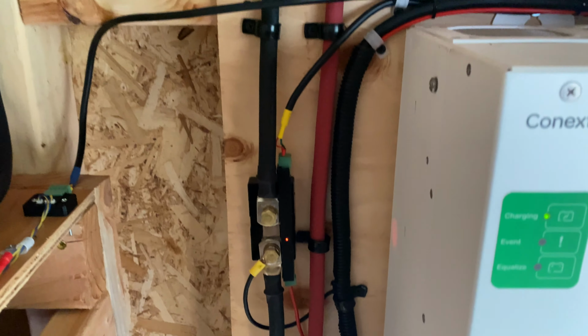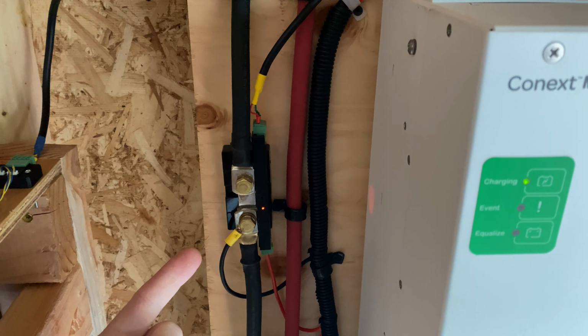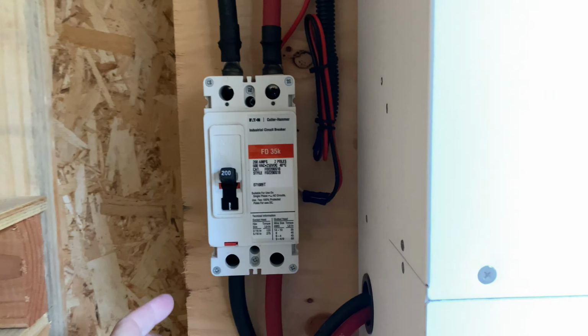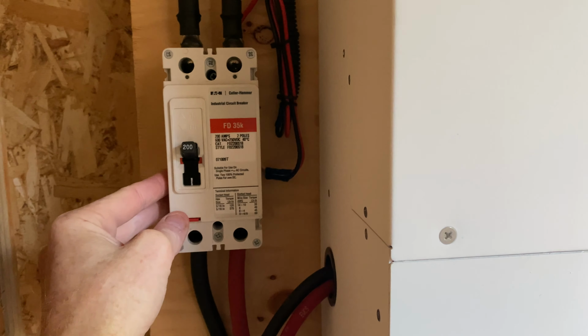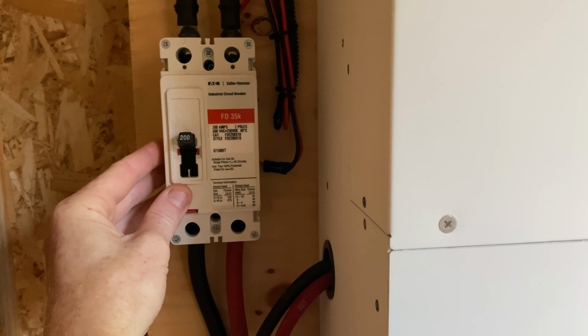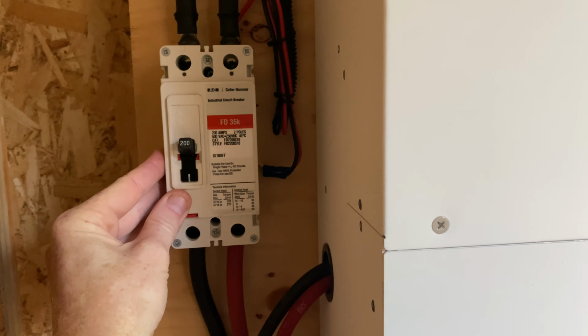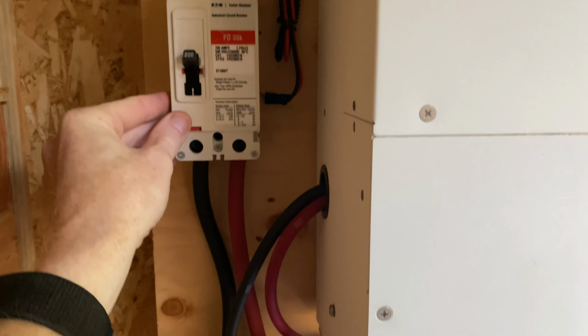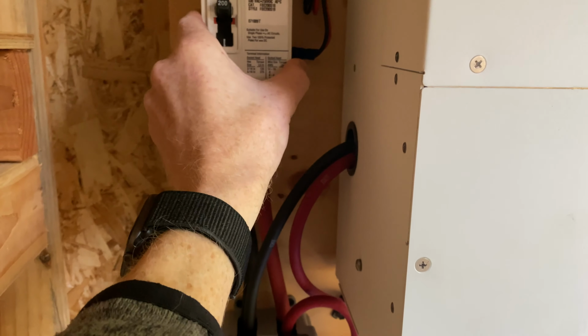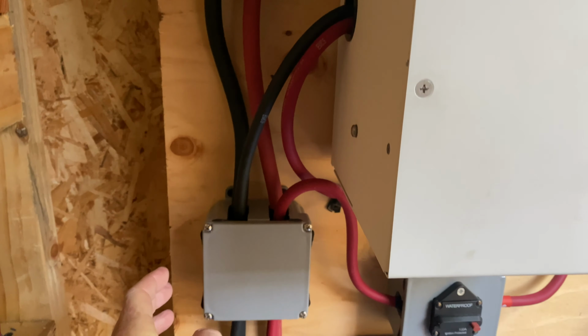If we continue on, obviously we have the shunt for the Batrium. Coming down here, we have the shunt trip breaker, which is controlled by Batrium as well, and this will disconnect all loads and the chargers and all that stuff in case of a critical event. This is 24 volt driven - we'll go into how that's done a little bit more in a bit.